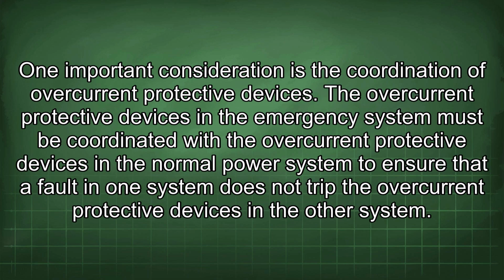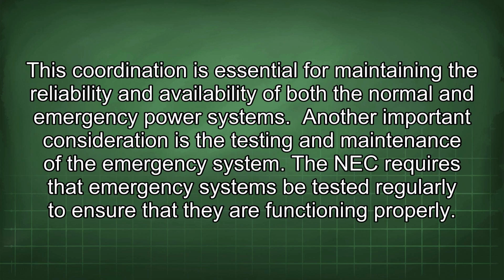One important consideration is the coordination of overcurrent protective devices. The overcurrent protective devices in the emergency system must be coordinated with the overcurrent protective devices in the normal power system to ensure that a fault in one system does not trip the overcurrent protective devices in the other system. This coordination is essential for maintaining the reliability and availability of both the normal and emergency power systems.